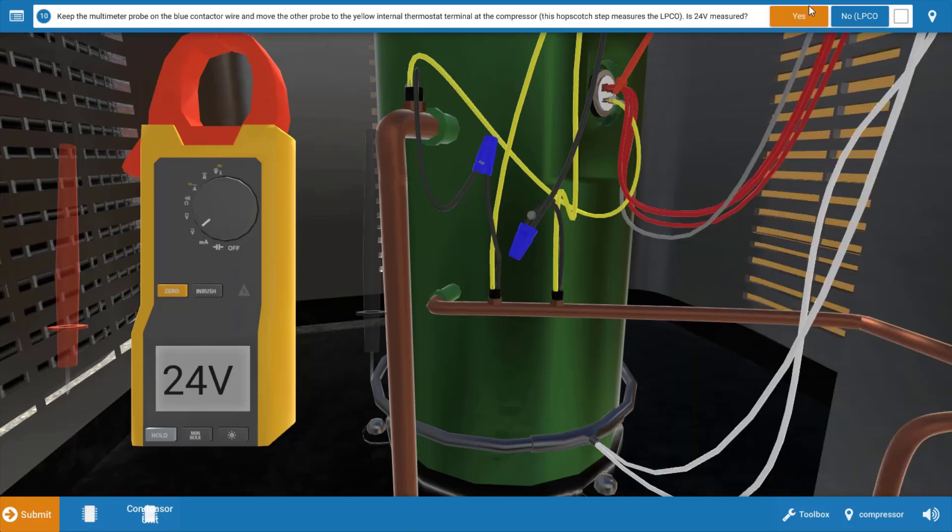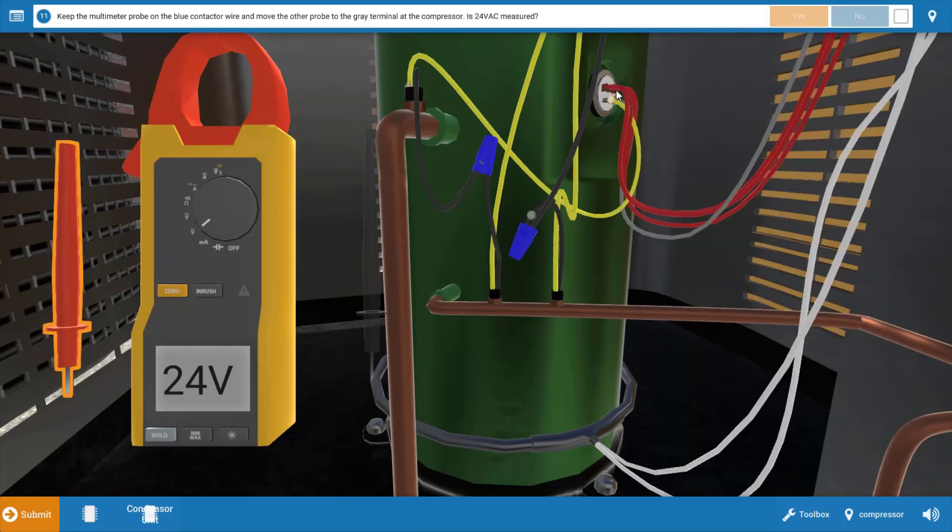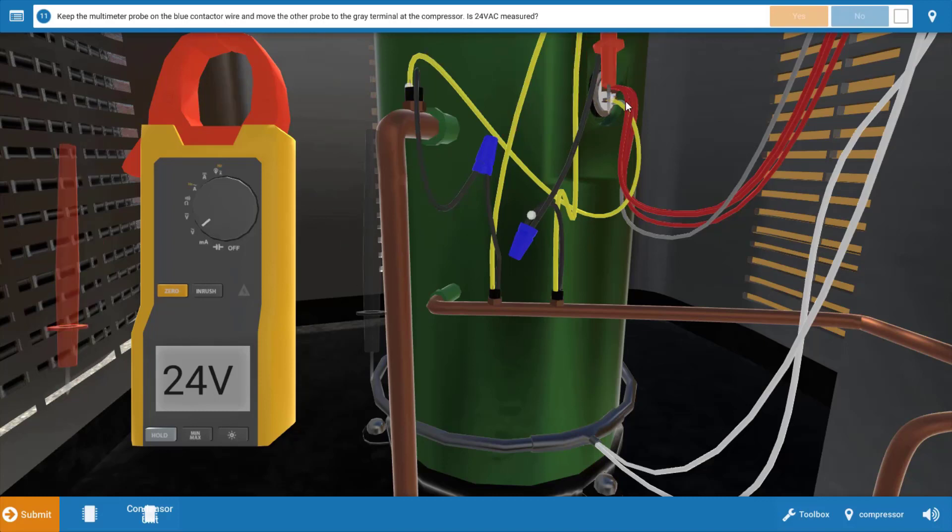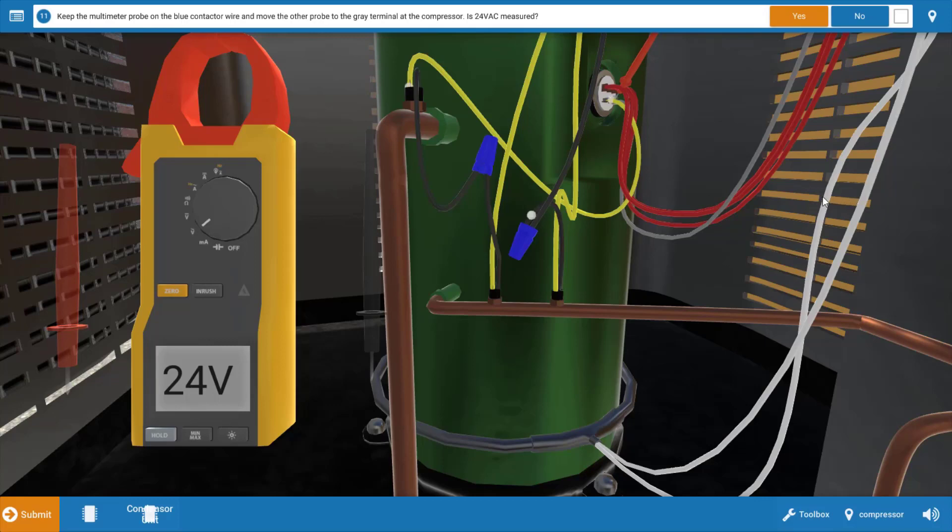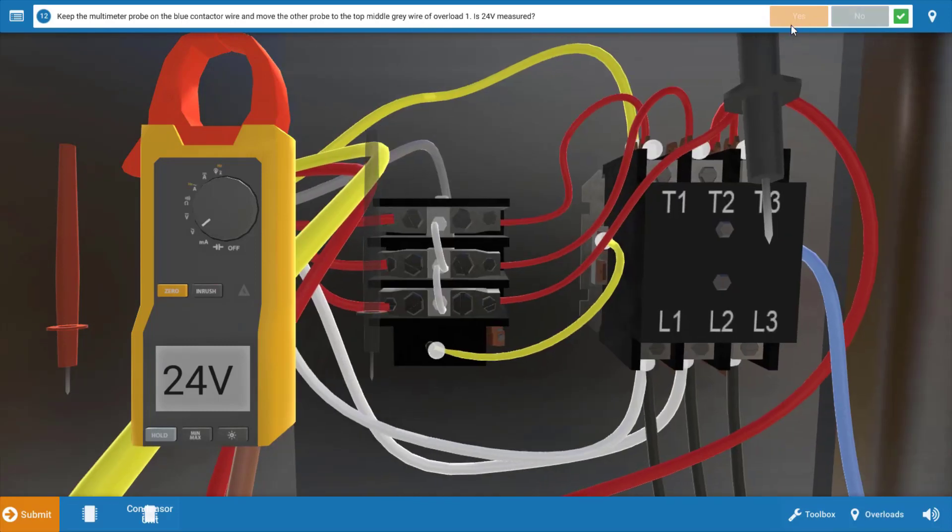After clicking yes on the procedure guide, we're going to move that lead to the other side of the internal thermostat and make sure we have power coming out of that. And in fact we do. So our internal thermostat checks out. We had power in, we've got power out, we can click yes.